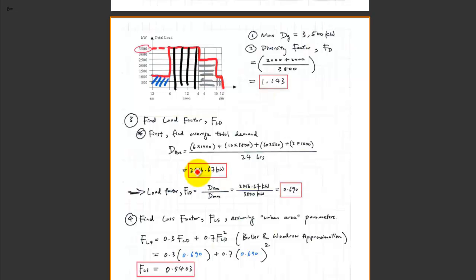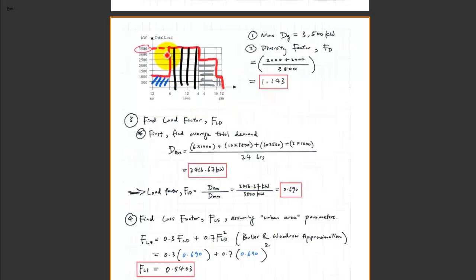Once you find the average of that curve, you find the load factor. The load factor is computed as the average divided by the maximum value. We already computed the average, and the maximum value of that demand is 3500, as found earlier. So the load factor is simply computed as 0.690.